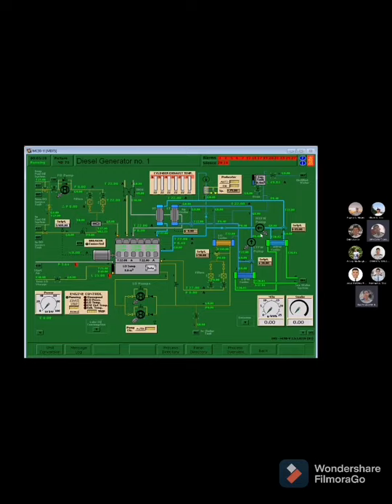Next, go to MD75 diesel generator number 1. Check the lube oil sump tank level: minimum level 30% and maximum 80%. The tank is okay. Open lube oil filter number 1. Next, manually start the lube oil priming pump. Done. Check the level of the expansion tank. Fill up the tank to normal level. If no water flow, go to MD67 and open the appropriate valves. Done. Switch on the electric preheater with a set point of 75 degrees Celsius. Done. Next, open number 1 diesel oil filter. Done.